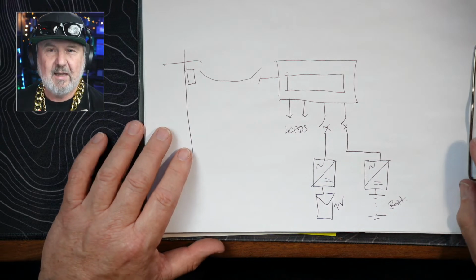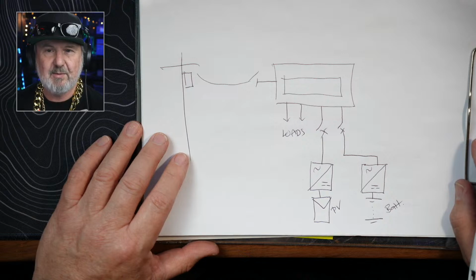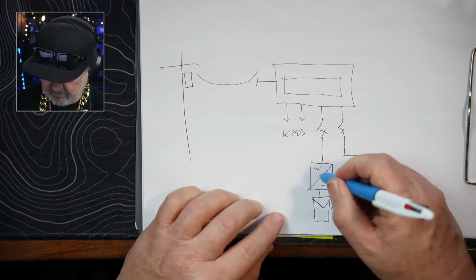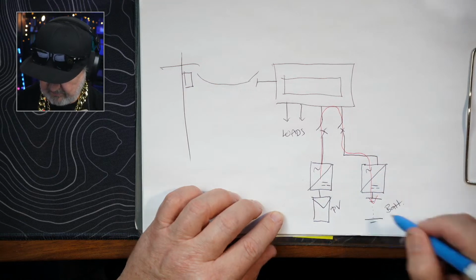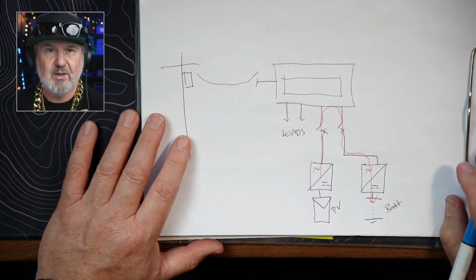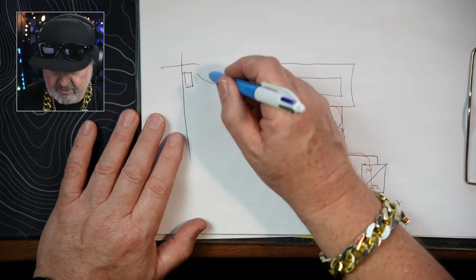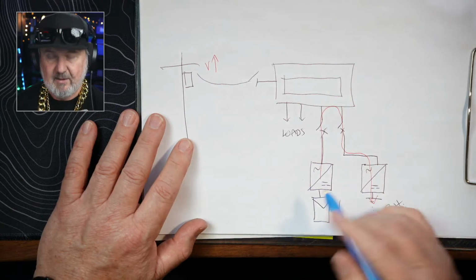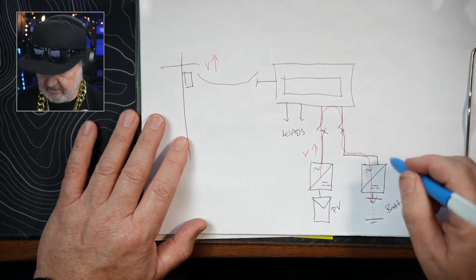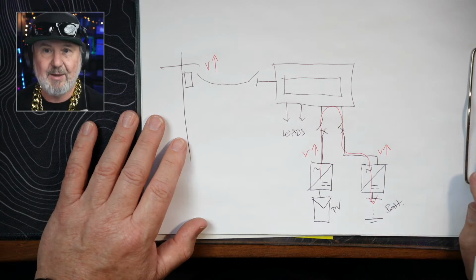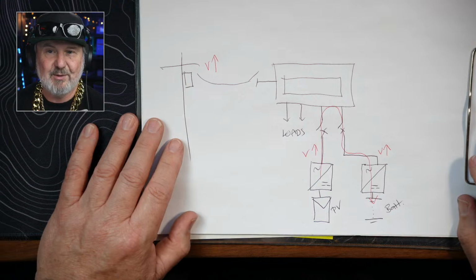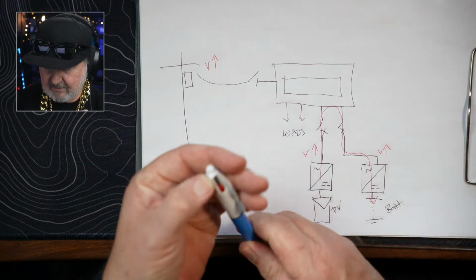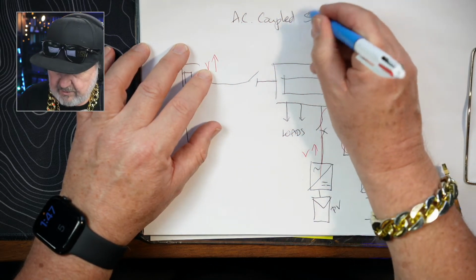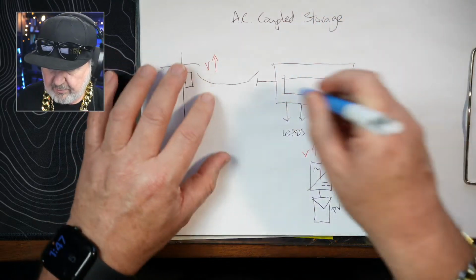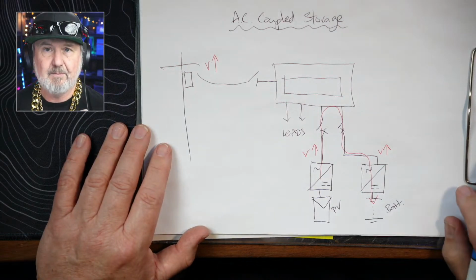Now, you might think, well, you said, Glenn, that having a battery actually helps because it means that you can send power to your battery rather than sending it out to the grid. True. But whenever the grid voltage goes up too high at this point, these inverters have to reduce their power just at the very time that you want them to charge the battery. So in this case, AC coupled storage may not avoid the problem of high grid voltage by charging a battery.